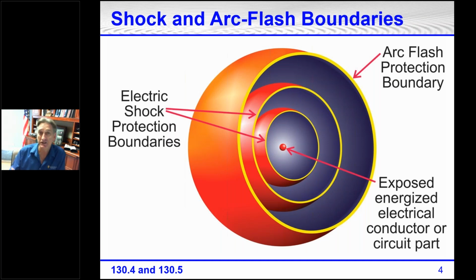I've personally seen equipment labels, the arc flash warning labels, with the arc flash boundary as close as 3 inches, an arc flash boundary 3 inches from live energized circuit conductors and parts. And I've seen a label as far away as 21.5 feet. So the arc flash boundary has nothing to do with the shock boundaries. It's just the way I made this drawing.